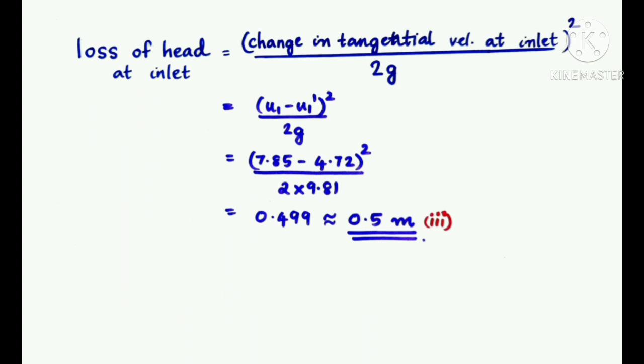Now, to find the loss of head at inlet, the formula is change in tangential velocity at inlet squared divided by 2g, which is equal to (U1 - U1')²/2g. Substituting the values, that is (7.85 - 4.72)² / (2 × 9.81) = 0.499 ≈ 0.5 m of water.